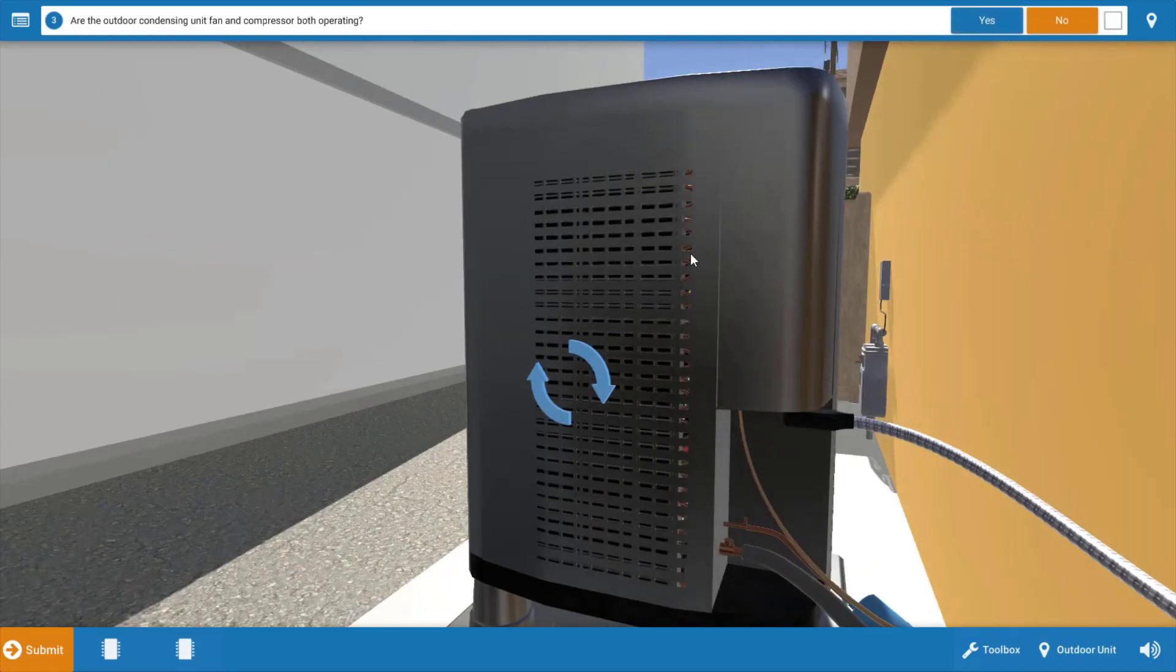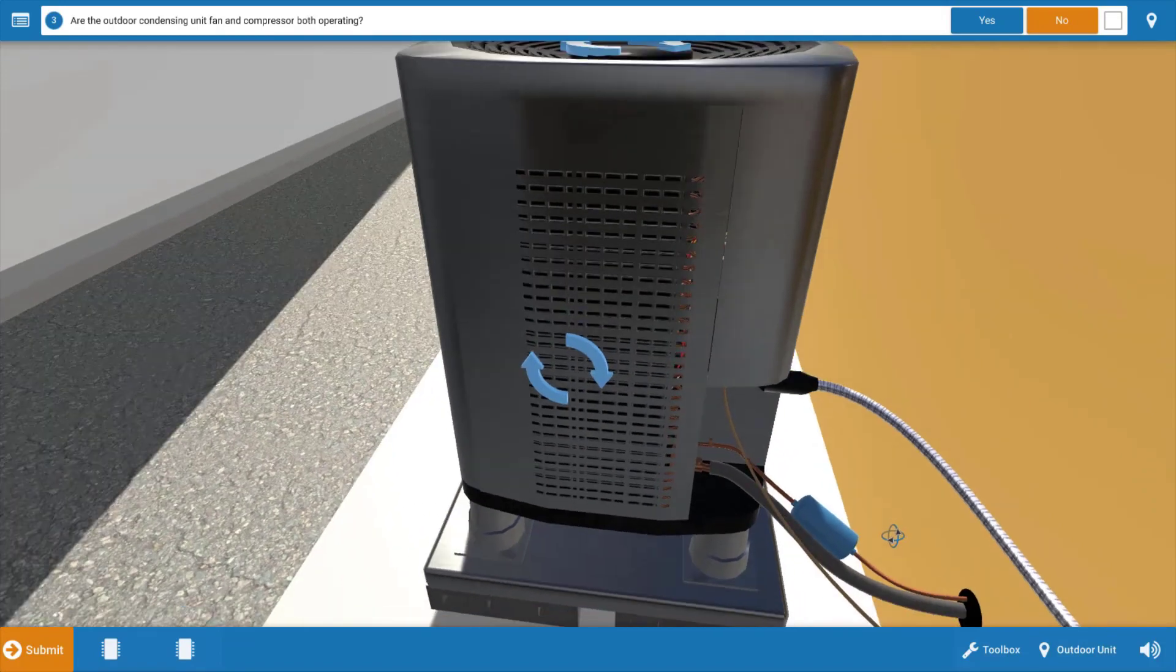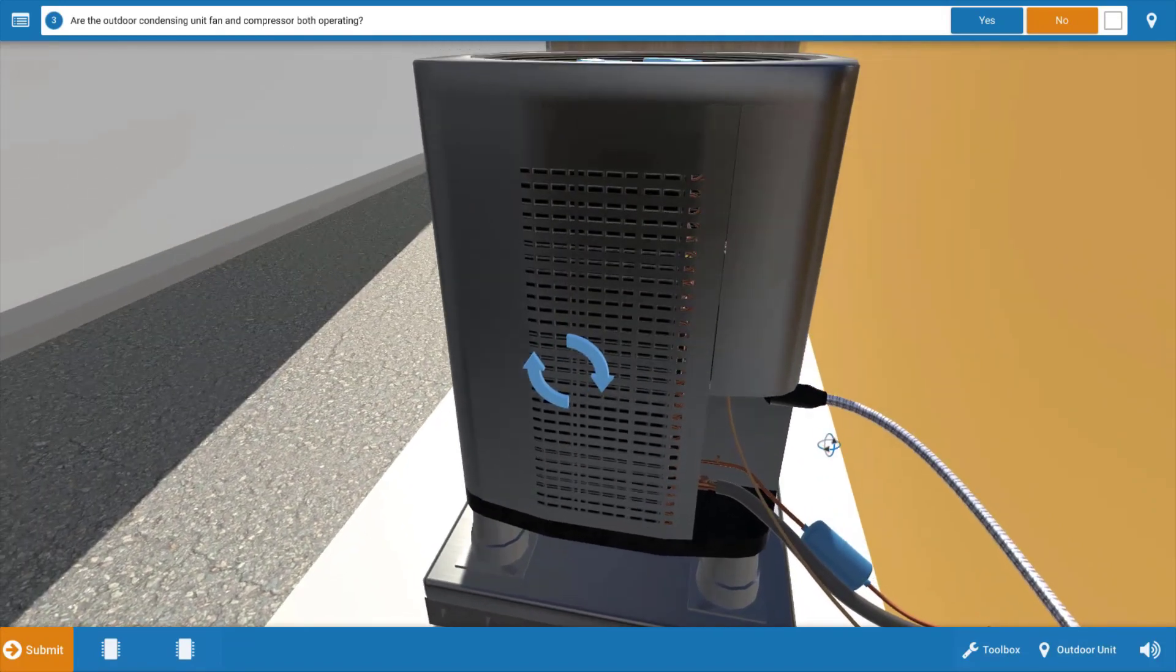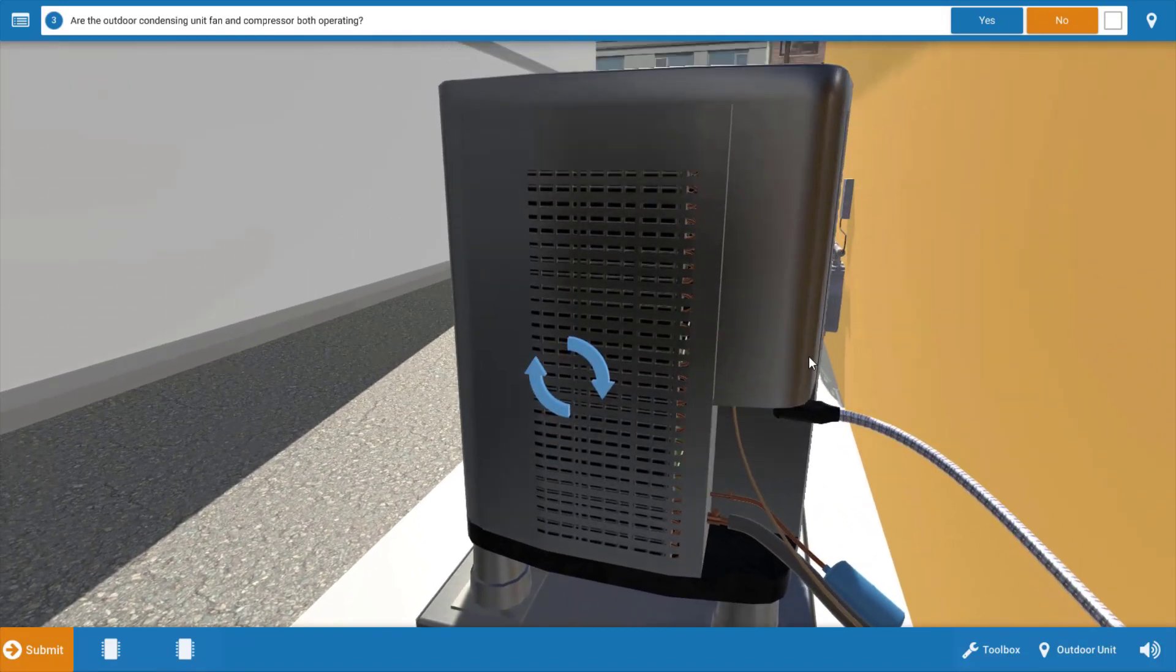Next we go to the outdoor unit and we can see here that neither the compressor nor the condenser fan is operating. So both of these motors are off as well as the indoor fan motor.